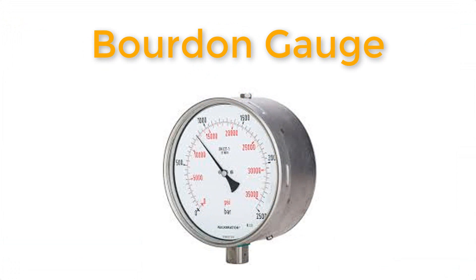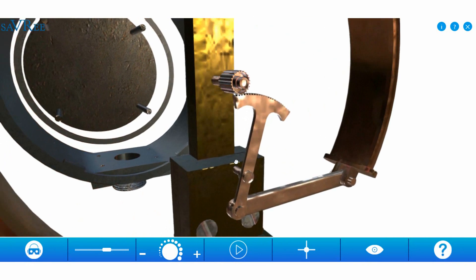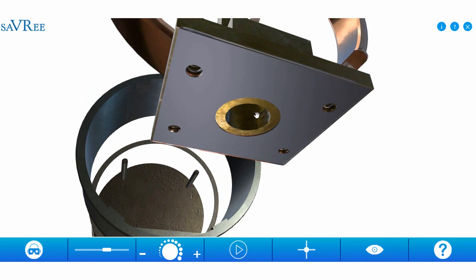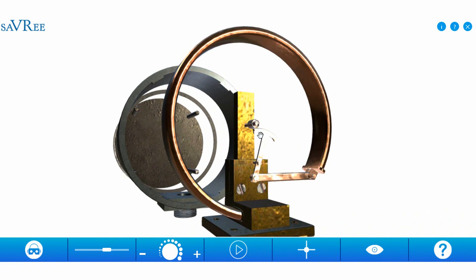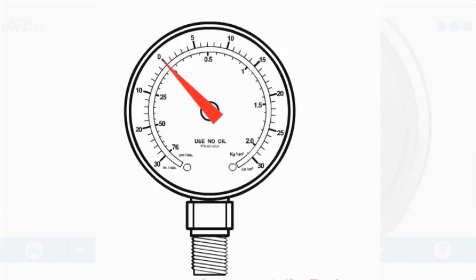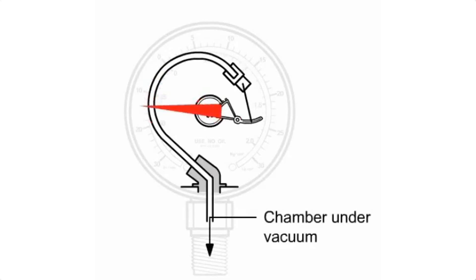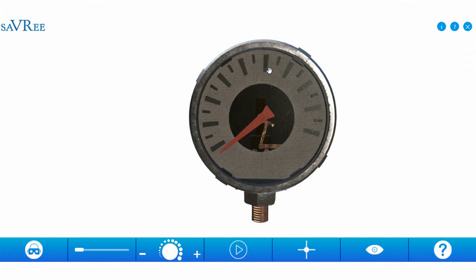Let's look at a bourdon gauge, used for local pressure indication. The bourdon gauge is connected to the system through a hole in the bottom. As pressure increases, the bourdon tube around the outside expands, pulling a lever and rotating a gear assembly, causing the pressure-indicating needle to turn. If pressure increases, the red needle turns clockwise; if pressure decreases, it goes the opposite direction. That's a bourdon gauge for local pressure indication.